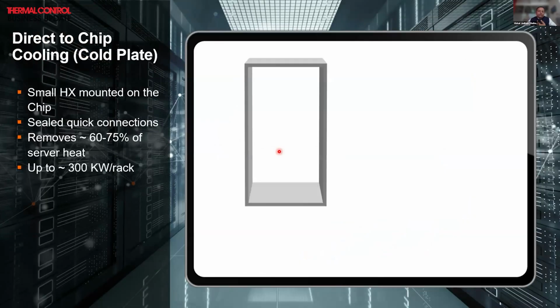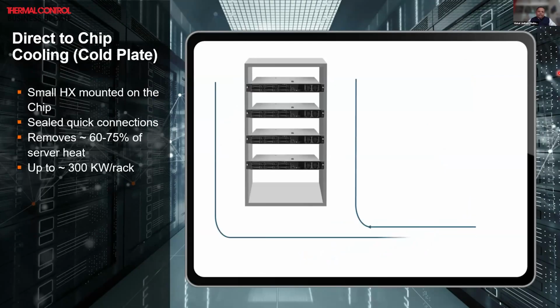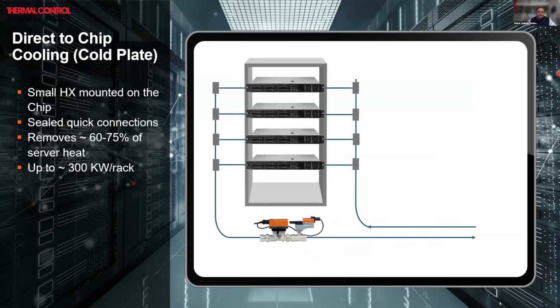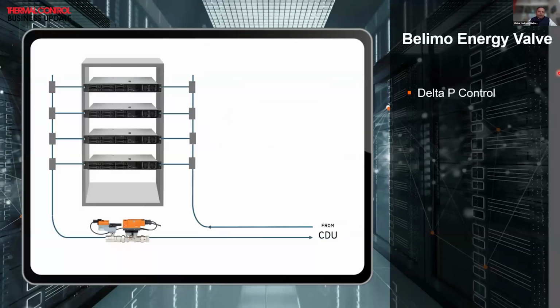One of the critical examples which I want to give here includes some of the mathematics, which I'm sure will be of interest to many of you. So this is, let's say, a rack which has four servers, and this is being supplied with chilled water, and then there is a Belimo control valve installed here. There is a feature in the Belimo control valve to modulate or control this with the help of delta T, or difference of temperature, or difference of pressure.